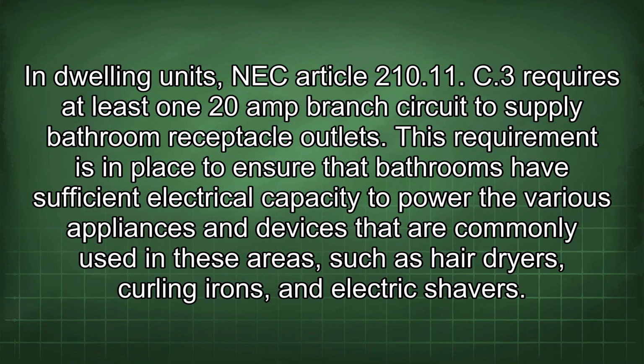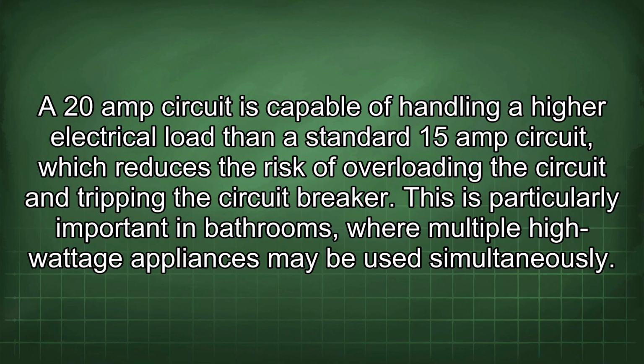This requirement is in place to ensure that bathrooms have sufficient electrical capacity to power the various appliances and devices that are commonly used in these areas, such as hair dryers, curling irons, and electric shavers. A 20-amp circuit is capable of handling a higher electrical load than a standard 15-amp circuit, which reduces the risk of overloading the circuit and tripping the circuit breaker. This is particularly important in bathrooms, where multiple high-wattage appliances may be used simultaneously.